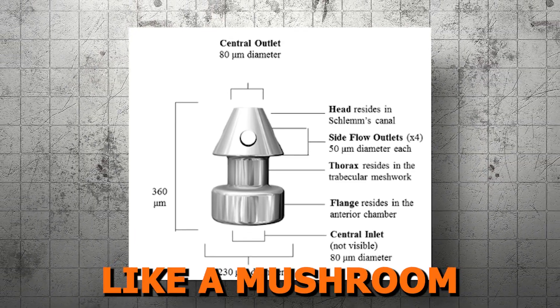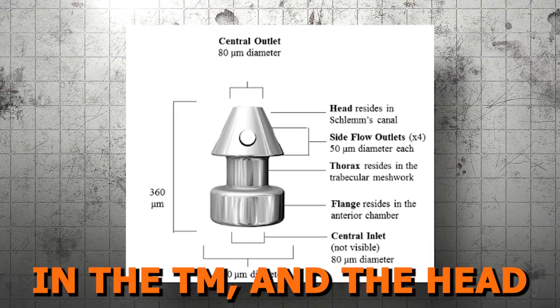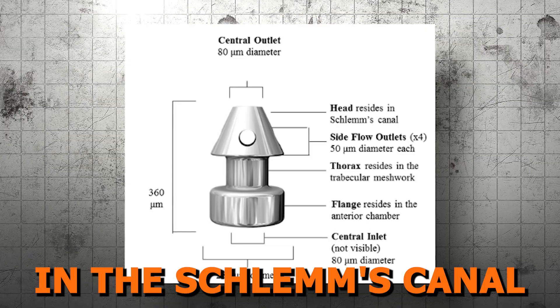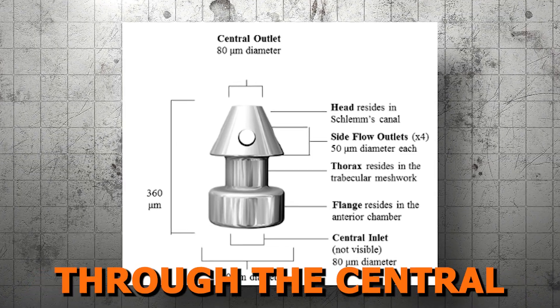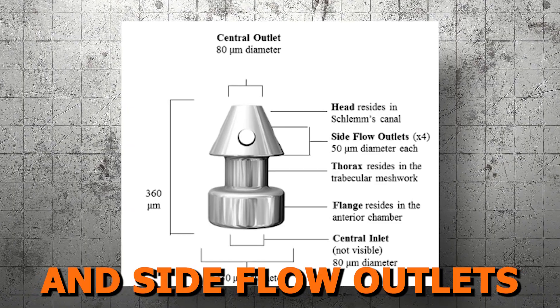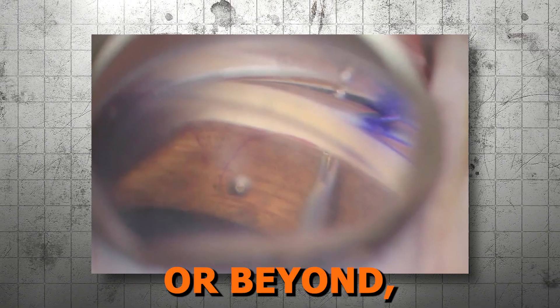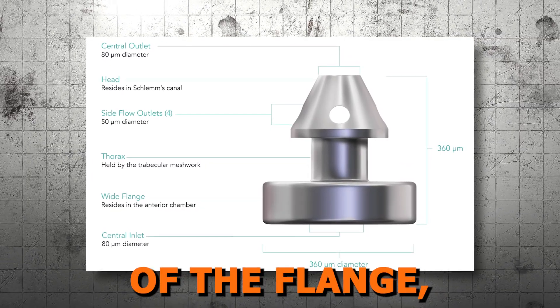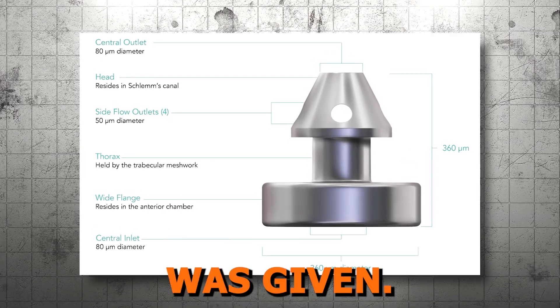It is designed like a mushroom with a flange that stays in the anterior chamber, a thorax that is lodged in the TM, and the head that resides in Schlemm's canal. The central inlet allows aqueous humor access through the central and side flow outlets that lead to Schlemm's canal. Due to the potential for over-implantation of the device, where it can get buried within the TM or beyond, a modification was made to increase the diameter of the flange, and a new name was given: iStent Inject W, for the wider flange.